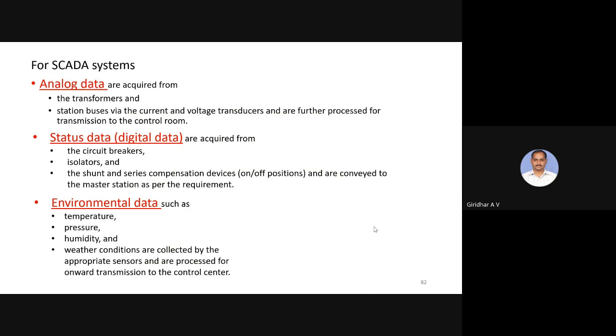So these are typical power line carrier equipments, and how they are connected. In the SCADA systems, basically analog data is acquired from the transformers and station buses via current and voltage transducers, processed in the control room, and converted into digital. Status data is also acquired, like circuit breaker status, the opening and closing status of the circuit breakers, isolators, and shunt and series compensation devices, their on or off positions, conveyed to the master station. These are all status data, digital data, and analog data from those CTs and PTs. Environmental data such as temperature, pressure, humidity, and weather conditions will also be passed on to the control center.